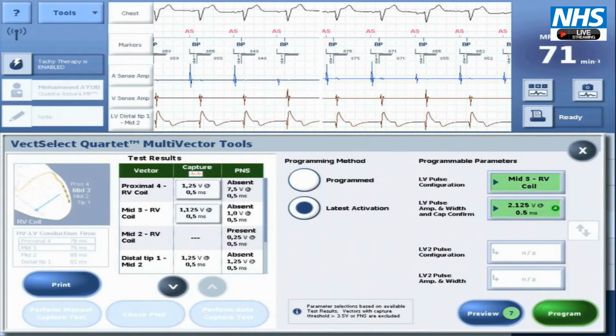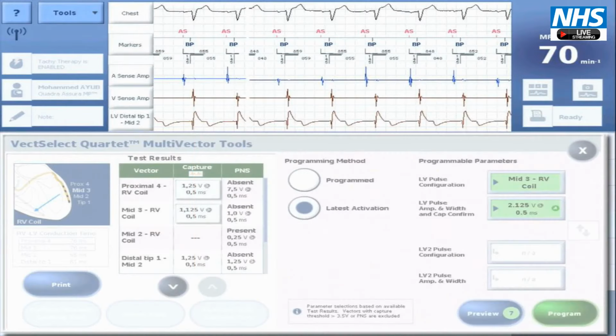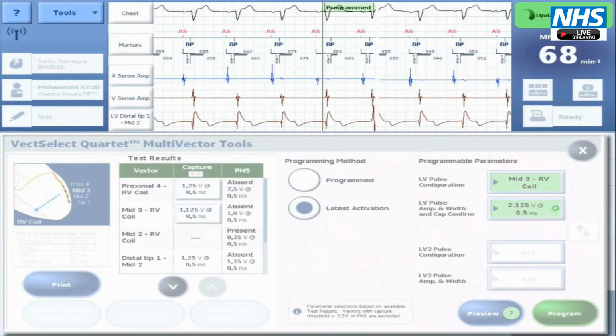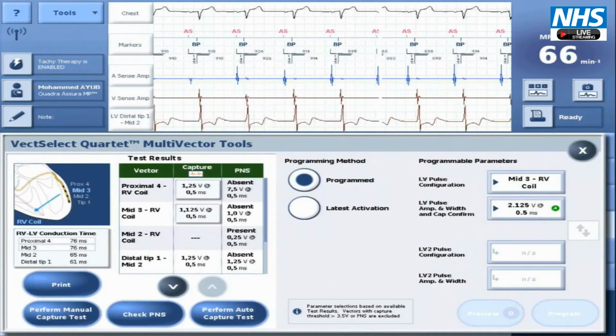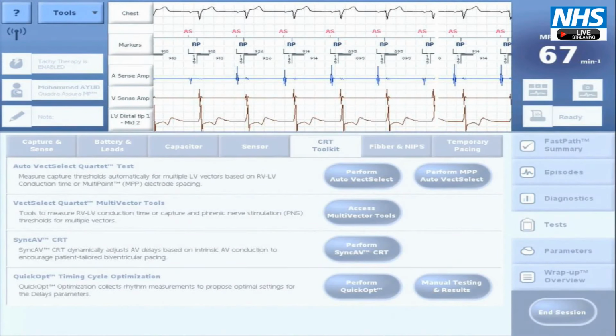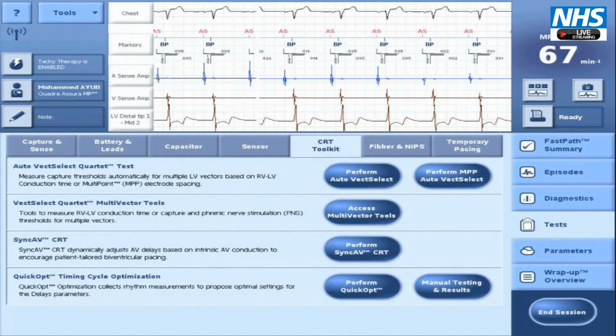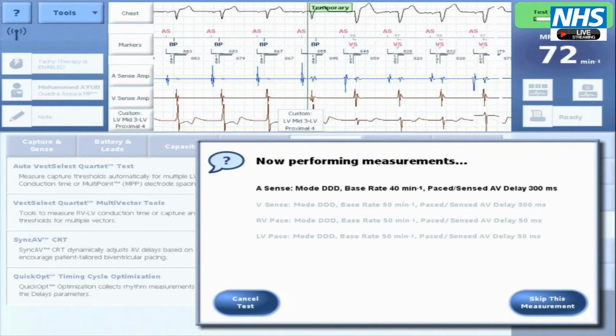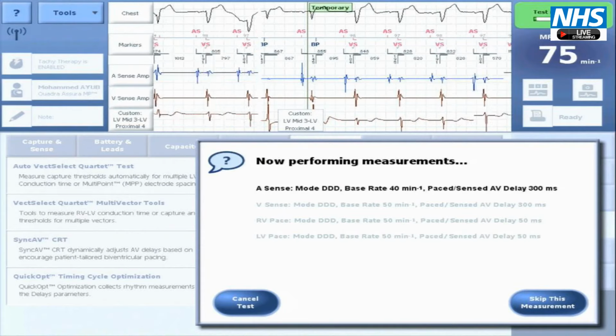Next, we would like to optimize the AV and VV delay. In this device, that is using QuickOpt. And Ashley's going to run the test for us now. So this algorithm attempts to give us an optimal AV and VV delay. For AV delay, it measures the P-wave duration to find the AV delay that allows optimal LV filling. And for VV delay, the algorithm attempts to cause LV and RV wavefronts to meet at an electrical midpoint between the RV lead and the selected LV electrode.